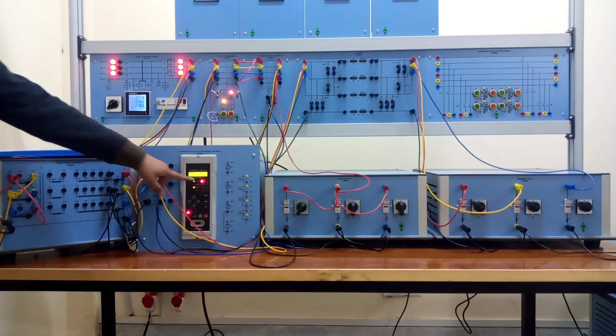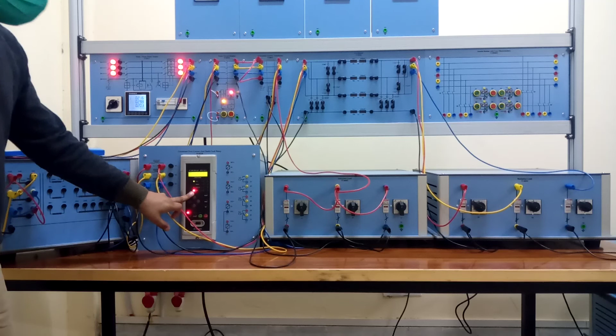Now you can see some current values on your current relay, and when you increase it, you will see a fault condition and the relay will trip. I'll show you in the zoomed version, but here you can see the relay has tripped. When I use this one, there is no fault now - you can reset the relay.